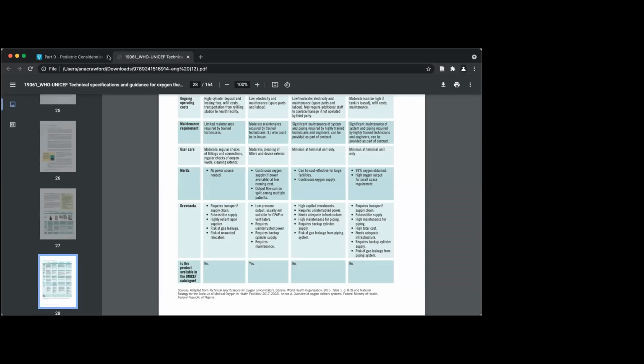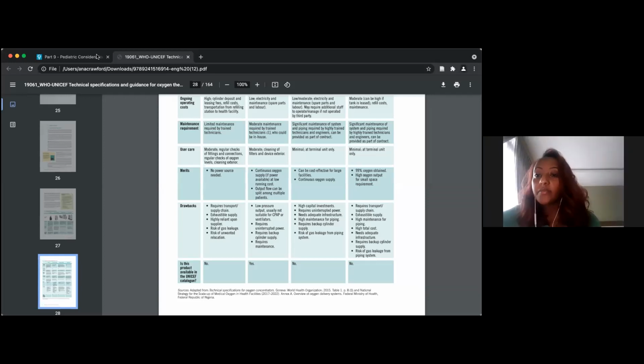The official recommendation is to have the cylinders secured at all times, whether they're strapped to the wall or in a specialized transportation device, if possible. Yes, thank you. So when it comes to concentrators, they are low pressure output devices, usually not suitable for CPAP or ventilators. So you use flow meters attached to them, and it requires uninterrupted power.